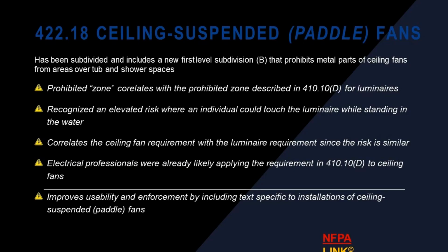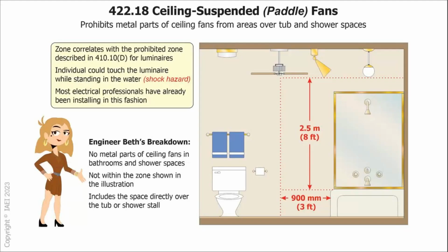All right. 422.18 is ceiling suspended paddle fans. This is another change. Okay. It's been subdivided and includes a new first level subdivision that prohibits metal parts of ceiling fans from over tub areas and shower spaces. So you can put the blades, but not the whole fan. Right? Well, if the blades aren't metal. So metal parts are prohibited over shower and tub spaces per the new 2023 code change cycle.